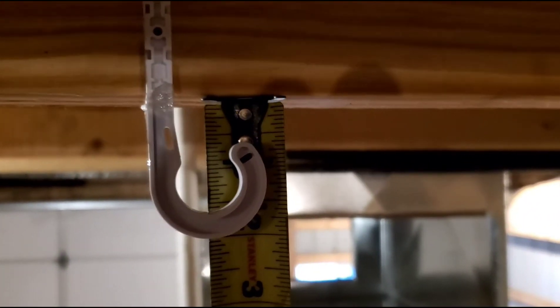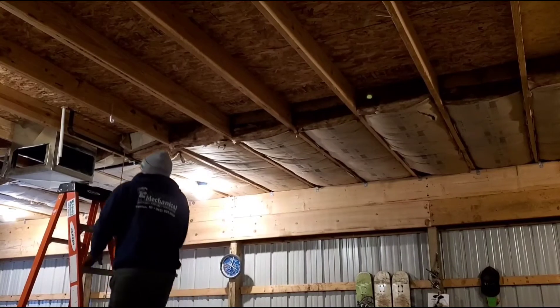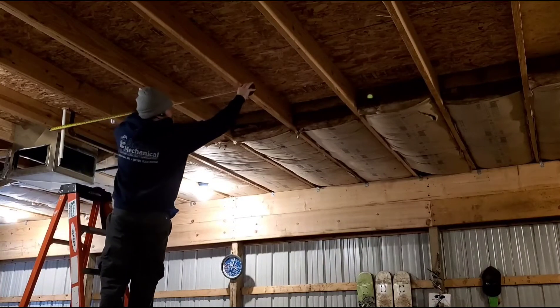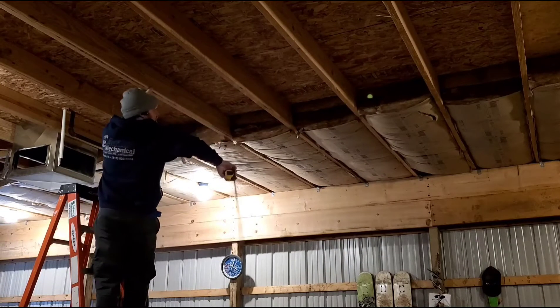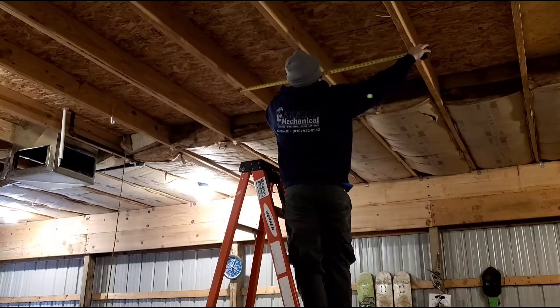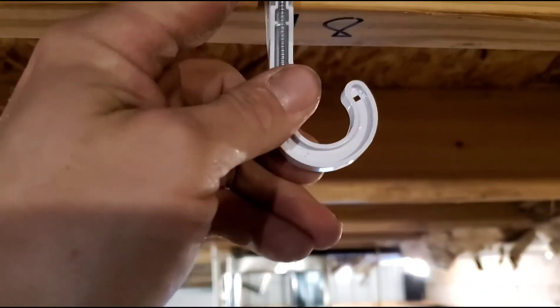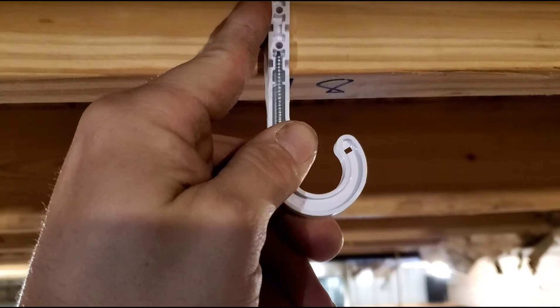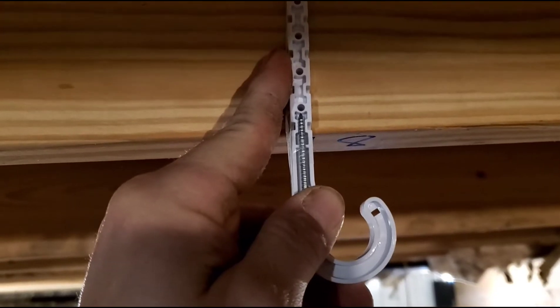From here it looks like we've got about inch and five-eighths. Let's get a measurement to see roughly where 10 foot is gonna get us. Got six feet right there, about eight — 10 foot's gonna be right there. Here's our eight-foot mark from where the pipe is. We're gonna add an eighth of an inch per foot, so we're gonna go two and five-eighths since our last measurement at that pipe was inch and five-eighths where the last J-hook was.